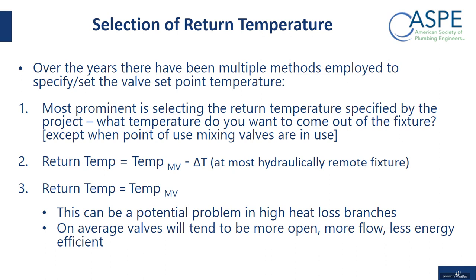There are people who are basically setting the return temp equal to the mixing valve temp. We all know there's going to be heat loss in the branches or risers. The theory here is if you set those the same with each other, then you will basically have that valve generally be more open than closed because you're going to have the heat loss and the valve is going to be trying to maintain that temperature. So the valve is going to tend to be more open. And I think the thinking there is now if you have the valve more in an open position, there's more flexibility as far as motion on either side of that temperature.